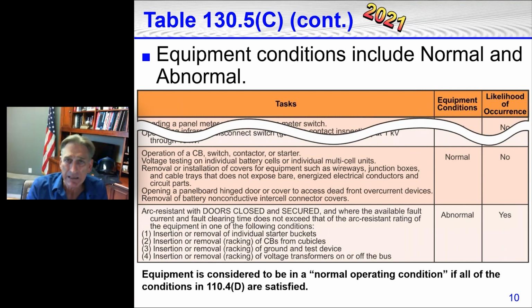Several cycles back, there used to be a category 0. Right now we have category 1, 2, 3, 4. Well, actually, at one point we had category 2 and 2 star or 2 asterisk, but back several cycles back, we used to have a category 0. Category 0, you had to wear clothing or shirts and pants of a certain material weight, like blue jeans and maybe a heavy duty denim shirt or a work shirt, but it did not have to be arc rated. Well, the committee got rid of category 0, and that's when they put in, all right, if the equipment is in normal operating condition, you do this. No arc rated PPE is required.